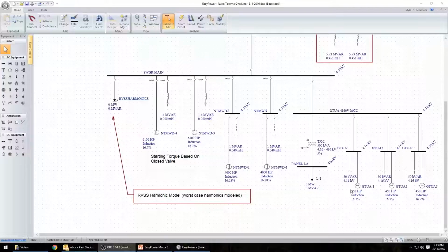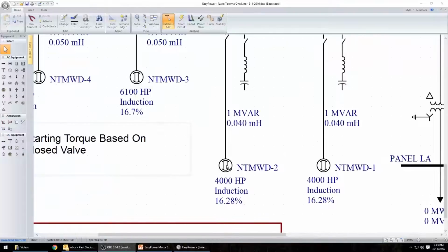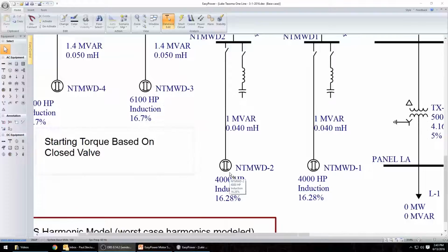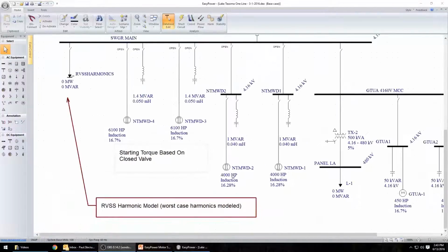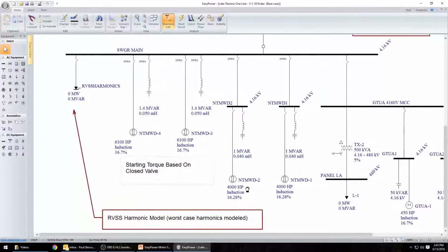So for some additional background, what was going on with this customer is it was an existing water pump station with two 4,000 horsepower pumps. These 4,000 horsepower pumps had no problem starting. They used some reduced voltage soft starts, and they had no problem starting. You can see here, based upon the symbol, that we do have these motors modeled as a dynamic load, and therefore they will perform dynamically during the dynamic analysis.